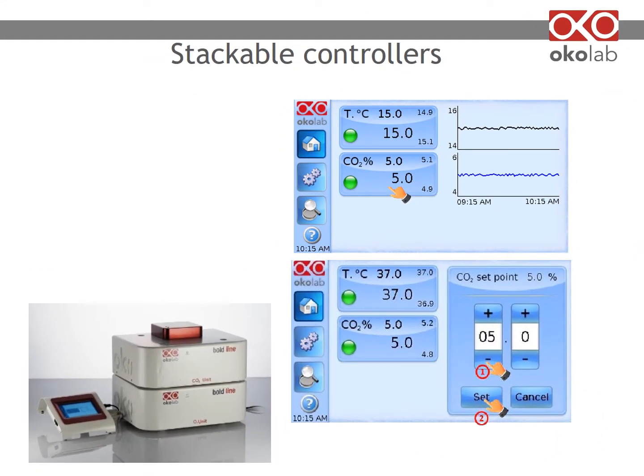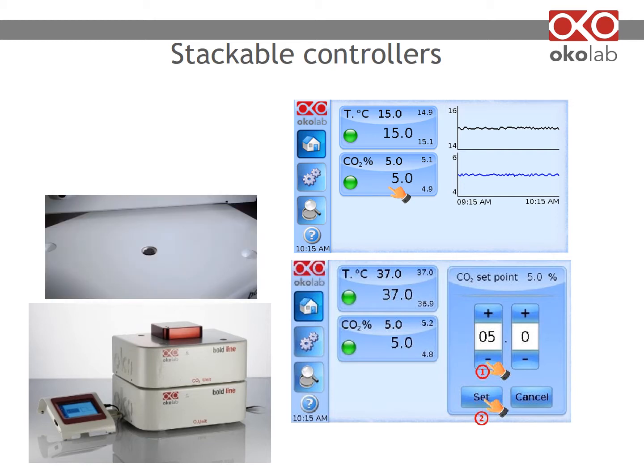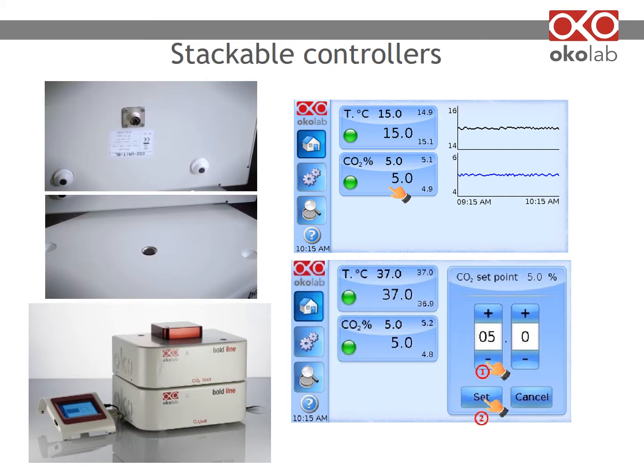To provide gas of the desired concentration, you can use an Okolab digital gas controller. Our controllers are integrated through cable-less connections — stack them on top of each other and the connection is established. A single touchscreen interface is used for a stack of controllers. Setting the desired concentration is intuitive: press on the CO2 tab and adjust by pressing plus or minus, then set.